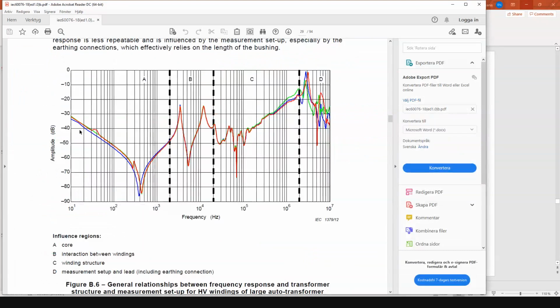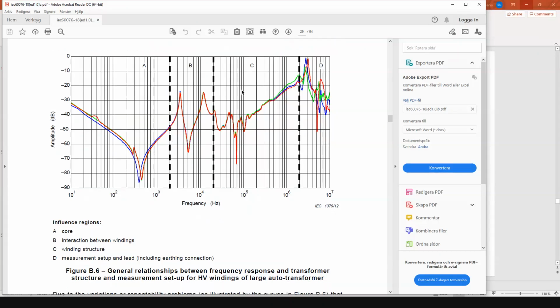Yes. Okay, so this is a standard of IEC, where we see the regions where core defects can be detected in a low frequency range. Then in the next range, there is interaction between windings, the winding structure at even higher frequencies, and above like 2 megahertz, then we have the measurement setup and grounding leads which influence the measurement. And if we have differences in our measurements in any of these parts, then we can roughly estimate that, okay, if we have an issue here, then it is the core. If it is an issue here somewhere, then it is more like a winding structure, something related to that.